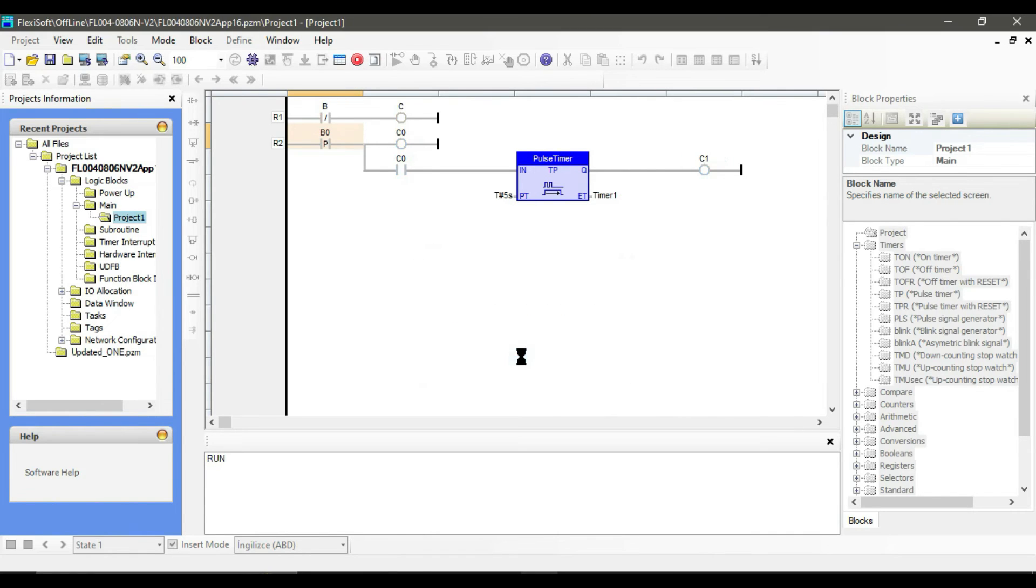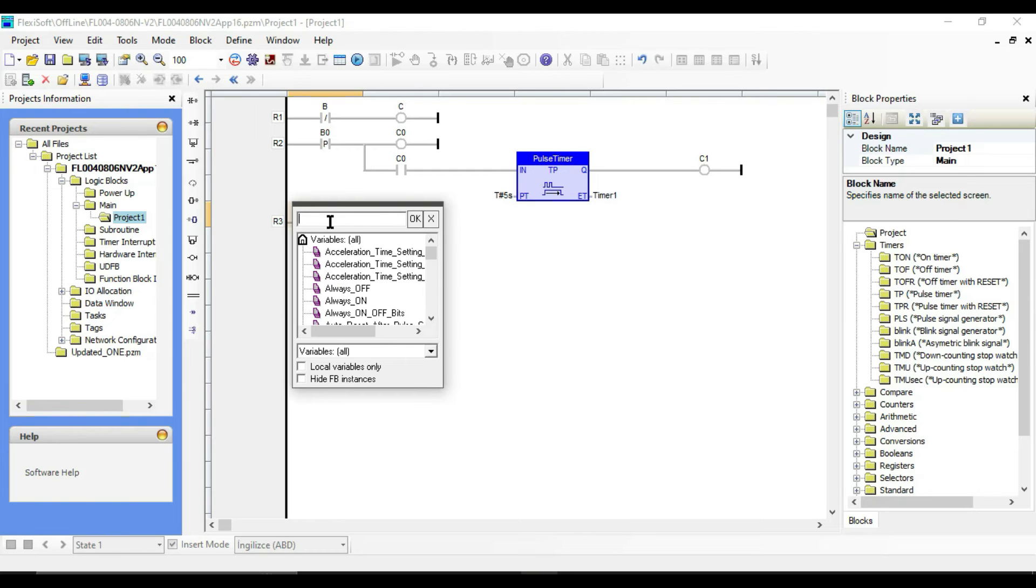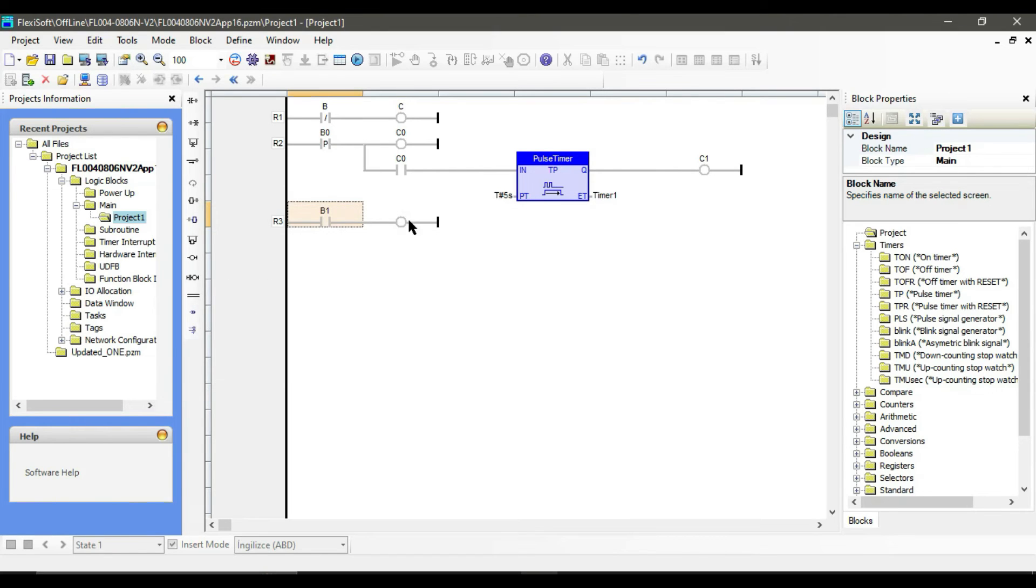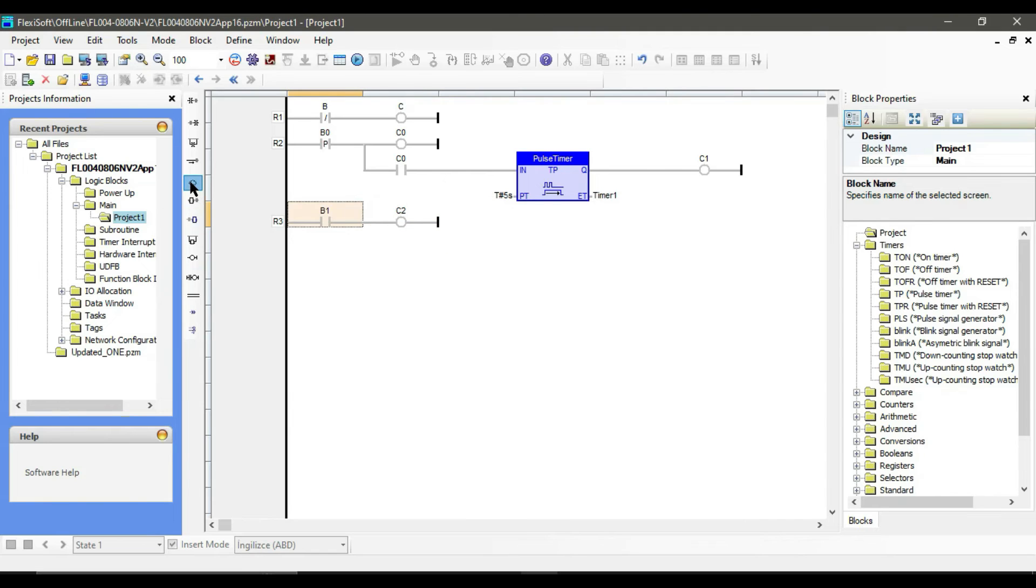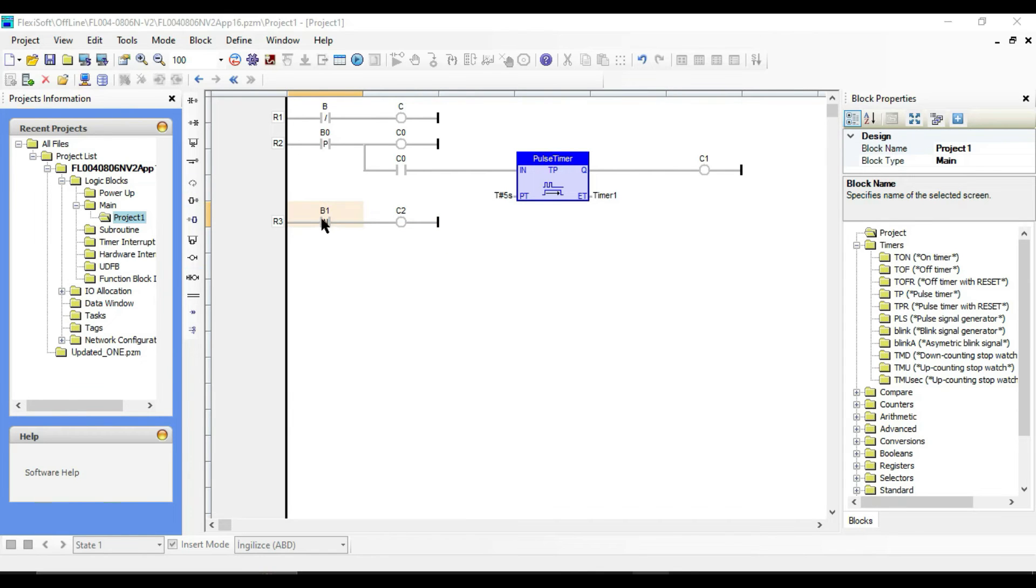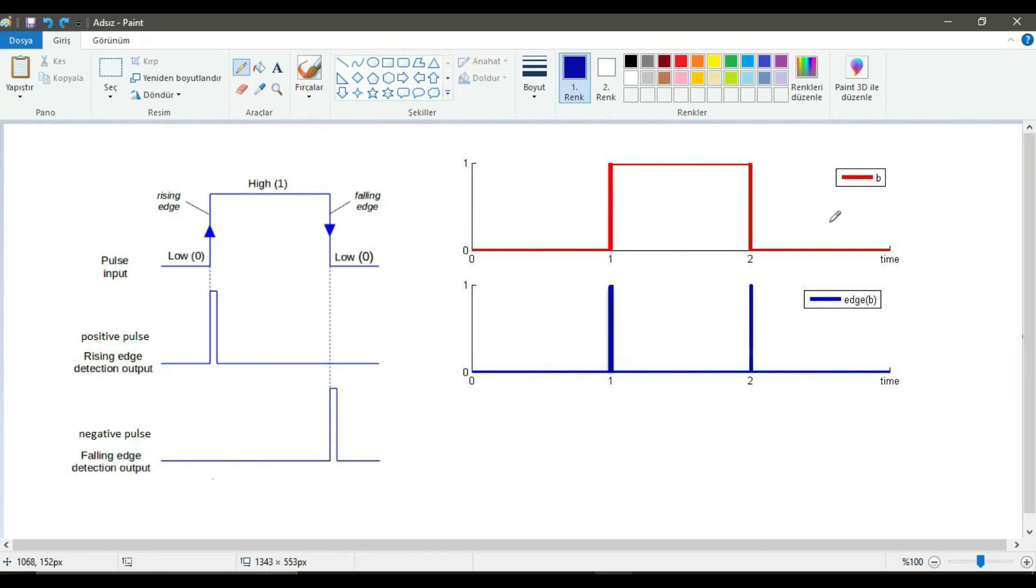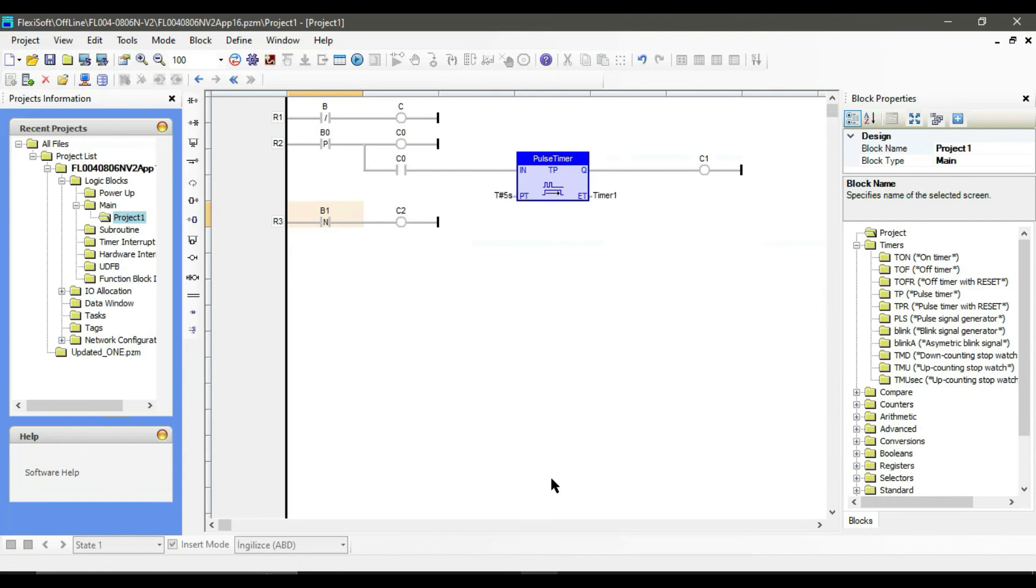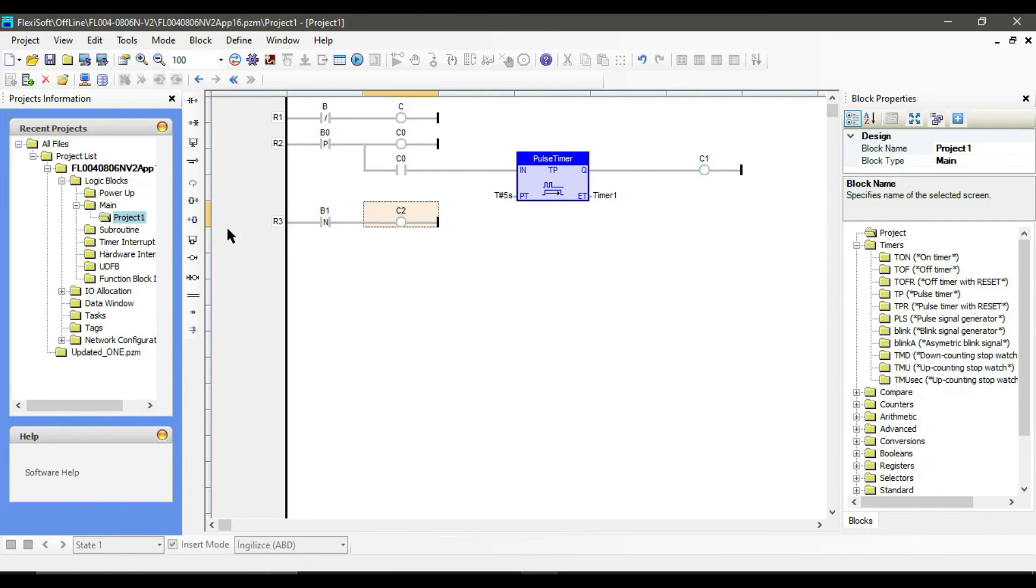There is also negative pulse, it is just the opposite of positive pulse. Contact is active during a scan cycle where the control bit has a falling edge, meaning detect the transition from 1 to 0. And the output is 1 only in the cycle where the clock goes from 1 to 0, otherwise is always 0. Let's create the same ladder logic as for positive pulse.